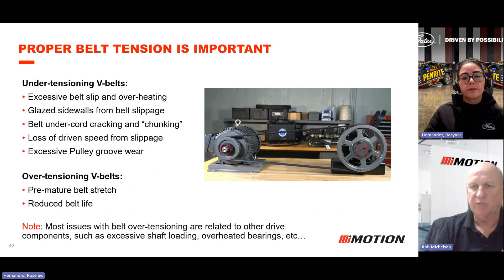When putting details into the program once you download it online, we need to install the kilowatts, RPM, current pulley sizes, belt section, number of belts, and belt length, and from that the program gives us the exact tension details required. The importance of this is that it also analyzes the drive as to whether it's oversized or undersized. If undersized, the belt will slip; if oversized, that could cause vibrations and poor performance. Undersizing and oversizing are just as bad as each other — we want the drive designed to its optimum performance, right in the sweet spot. That's why we use the programs, and why the accuracy of tension is also critical to give it the best possible life.